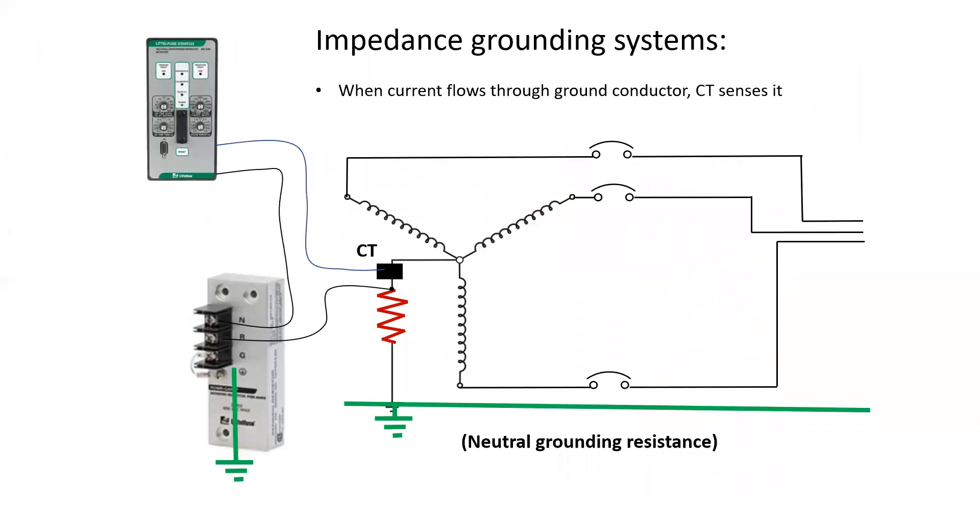Impedance grounding systems will use a CT to monitor when there's current flowing on this ground conductor. And we put a large chunk of resistance in series with the ground conductor, and the CT will register when current flows through it and send that signal off to the control module. So CTs are used in lots of situations where I simply want to know, is there current? Is there no current?